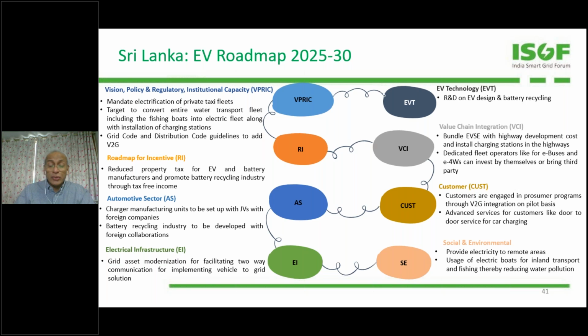Basically, V2G should happen on AC charging—AC Type 2 charging should allow V2G. This is exactly like an inverter function. You charge the vehicle, plug it onto the AC charger, program it so that when electricity on the grid is cheap, you buy it, and when the price is more than X rupees or X cents, you sell it, but keep enough to drive 20 or 50 kilometers. For the V2G function, charging and discharging between 70% to 90%, or 90% down to 60%, is fine, any number of times, whenever grid support is required. Whenever a signal comes from the grid operator, you pump electricity back to the grid, and after that signal stops, you buy from the grid again and go back up to 90% or 95%.